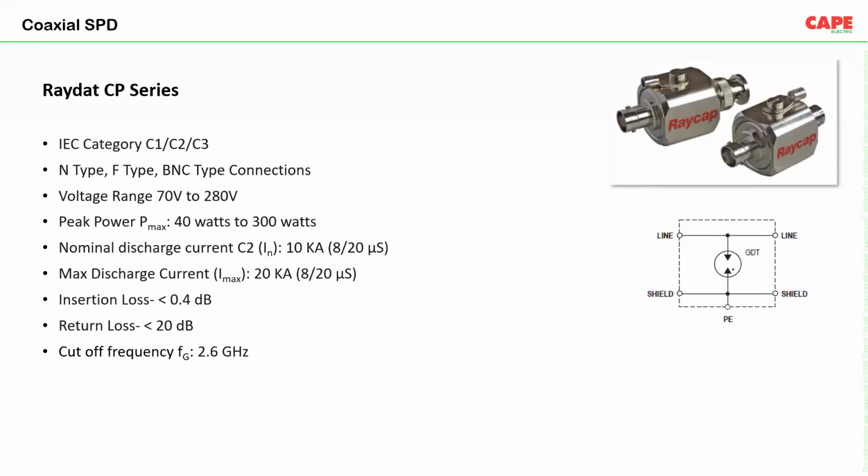They have their... what is the right word? They have this chalky something on the mountain. So they communicate with other services, other places through these radio transmitters, and they were experiencing a really common failure. So once we had supplied this kind of product, this kind of coaxial SPDs, the failure in their segment was practically zero. Earlier, without SPDs, they were experiencing failure almost every time there was lightning or thunder.